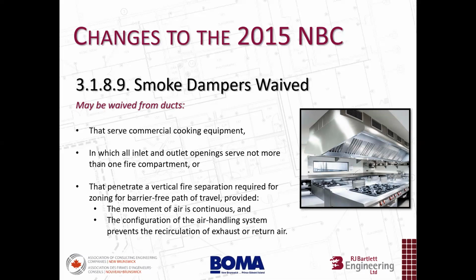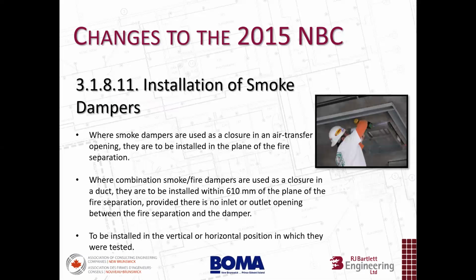Another instance where they're waived is where they penetrate a vertical fire separation required for zoning for barrier-free path of travel, provided a couple of conditions: that the movement of air is continuous and the configuration of the air handling system prevents the recirculation of exhaust or return air. So for the installation of smoke dampers, where smoke dampers are used as a closure in an air transfer opening, they are to be installed in the plane of the fire separation. Where combination smoke fire dampers are used as a closure in a duct, they're permitted to be offset somewhat, but just to a maximum of 610 millimeters from the plane of the fire separation, provided there's no inlet or outlet opening between the fire separation and the damper.